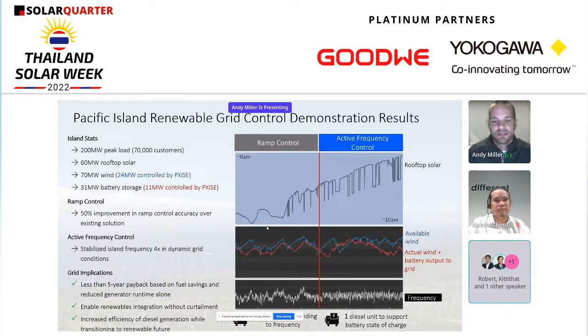But what's most interesting about this use case is using that energy storage asset not just to solve a local objective of ramp control, but to actually manage the supply and demand balance of the entire island. This island, with its high amount of renewable energy, was having a hard time keeping the grid in balance, reflected in fluctuations of the island's frequency. This matters because if frequency fluctuates too low, it actually creates power outages.